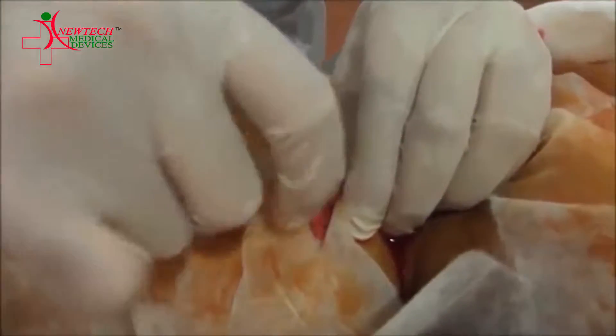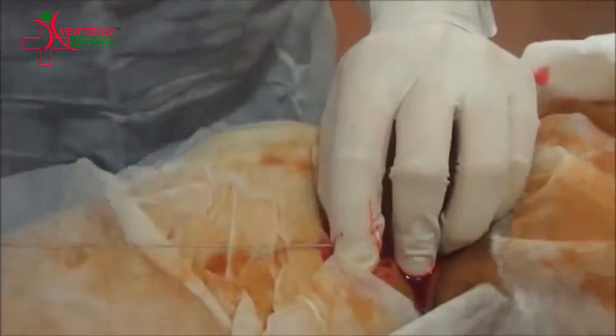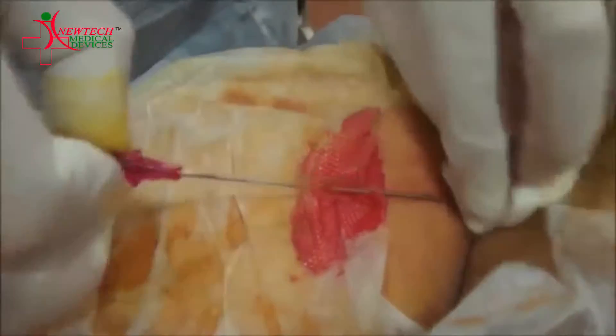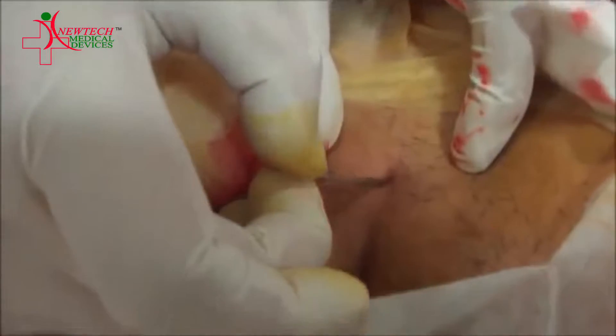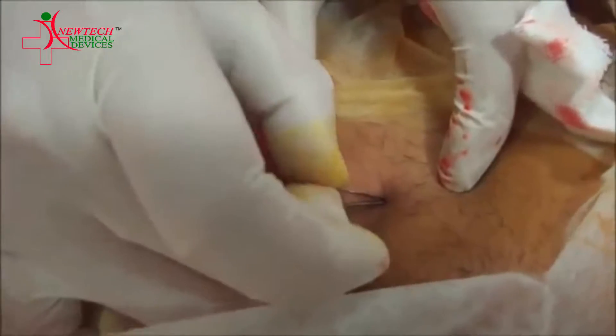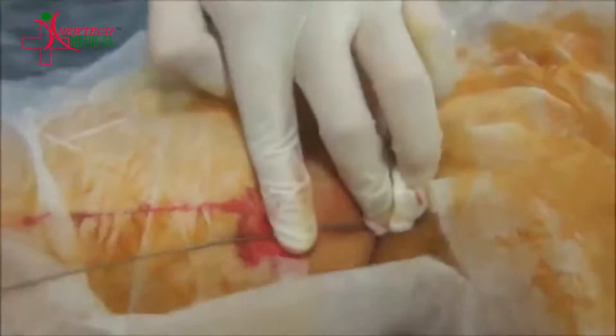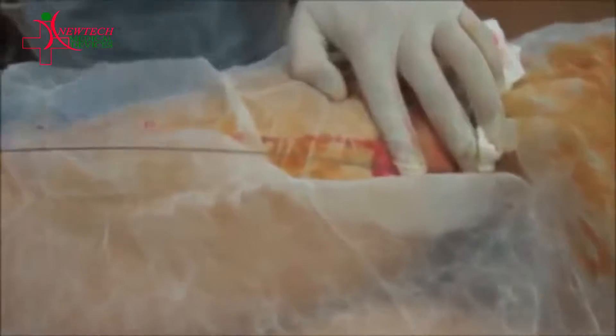The guide wire can be made up of stainless steel 304 or nitinol — both are body-friendly materials. Once the guide wire is inserted through the introducer needle, the role of the introducer needle finishes and the nephrologist removes it. Our guide wires meet all international standards; they are smooth, flexible, kink-resistant, and biocompatible. After removing the introducer needle, a small incision is made with a scalpel blade so that a dilator can be inserted over the guide wire to dilate the opening.